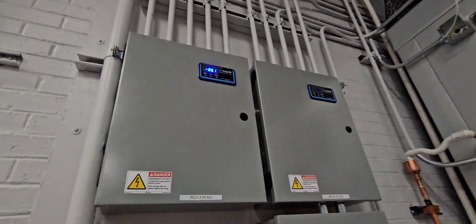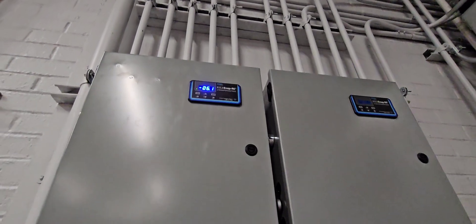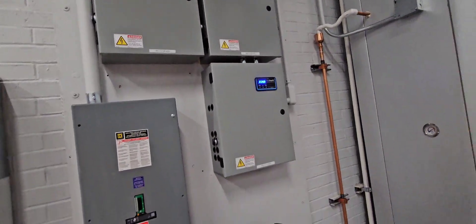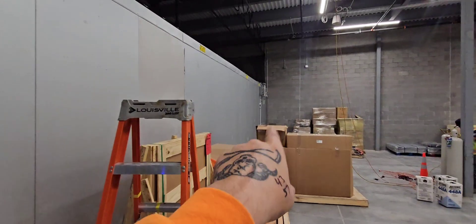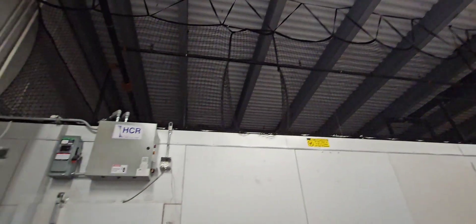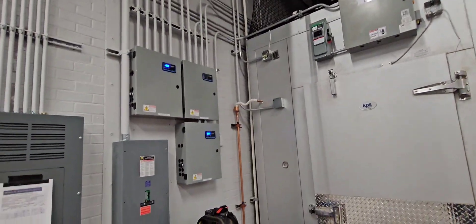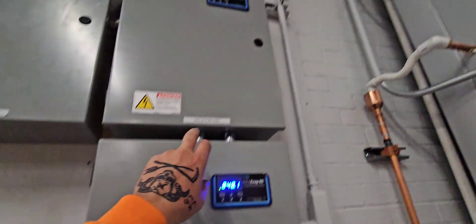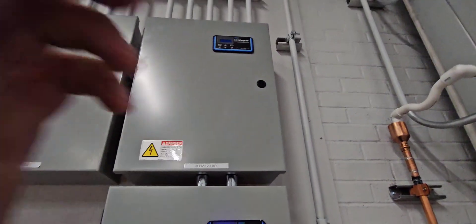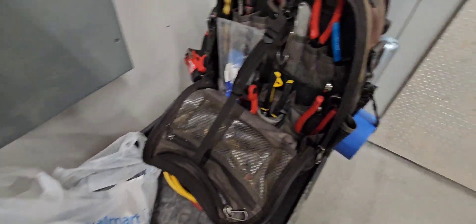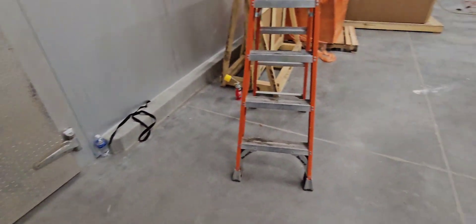So I let this thing run overnight. It's at negative six, was at negative eight when I got here, which is set point. I already checked superheat inside the box. I checked compressor superheat on the roof, made sure the pressure controls were all set. So I think that's it for this one. You can see we also got this box running last night and then tonight I'm doing that one. So that's it for this video. As always I appreciate the support, like subscribe share, and have a good one. Later.